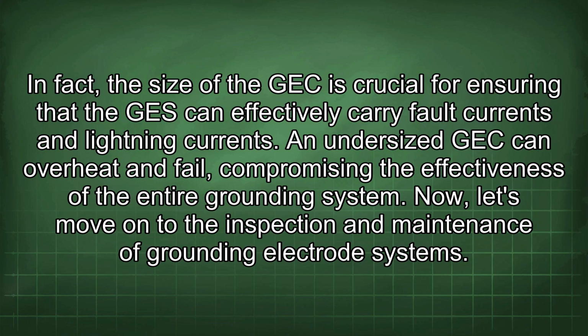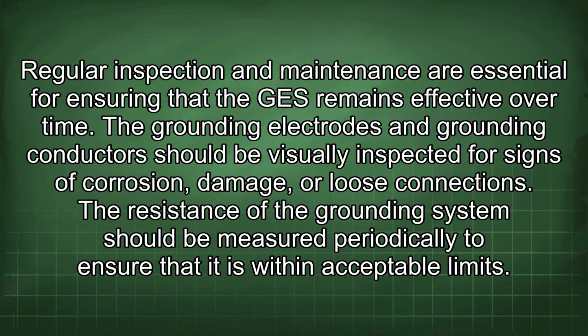Now, let's move on to the inspection and maintenance of grounding electrode systems. Regular inspection and maintenance are essential for ensuring that the GES remains effective over time. The grounding electrodes and grounding conductor should be visually inspected for signs of corrosion, damage, or loose connections. The resistance of the grounding system should be measured periodically to ensure that it is within acceptable limits.